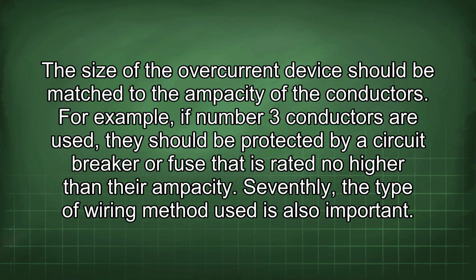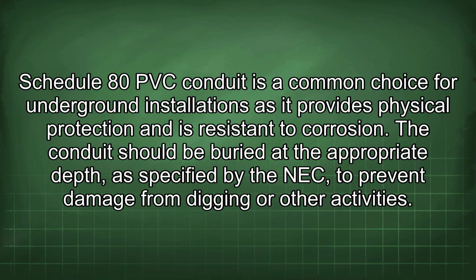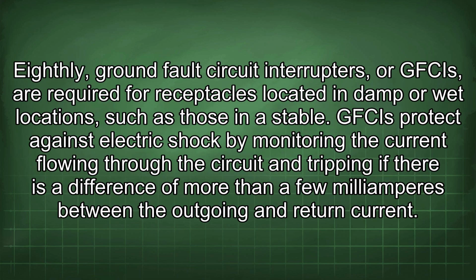Seventhly, the type of wiring method used is also important. Schedule 80 PVC conduit is a common choice for underground installations as it provides physical protection and is resistant to corrosion. The conduit should be buried at the appropriate depth, as specified by the NEC, to prevent damage from digging or other activities. Eighthly, ground fault circuit interrupters, or GFCIs, are required for receptacles located in damp or wet locations, such as those in a stable.